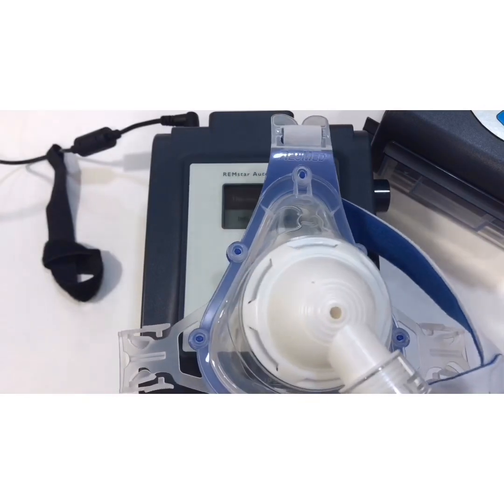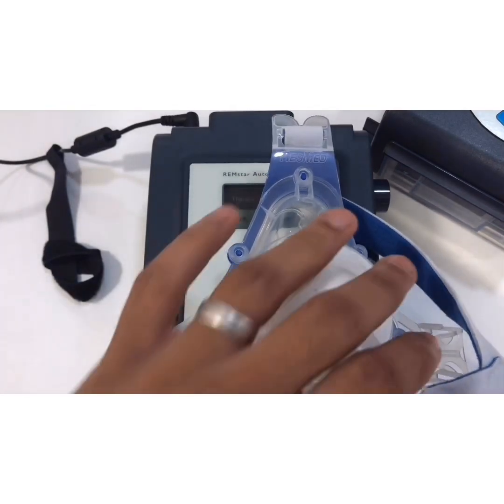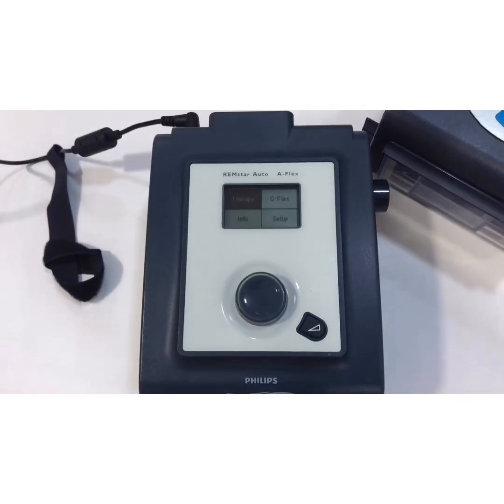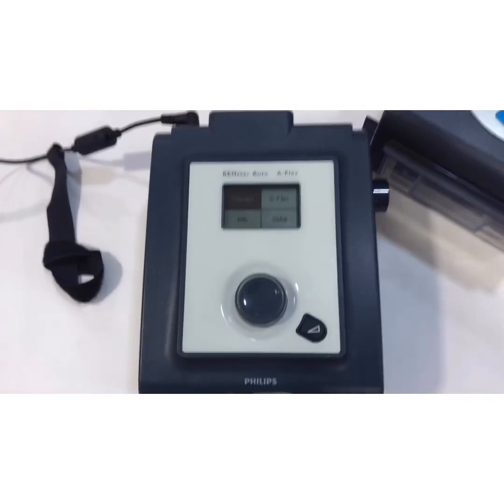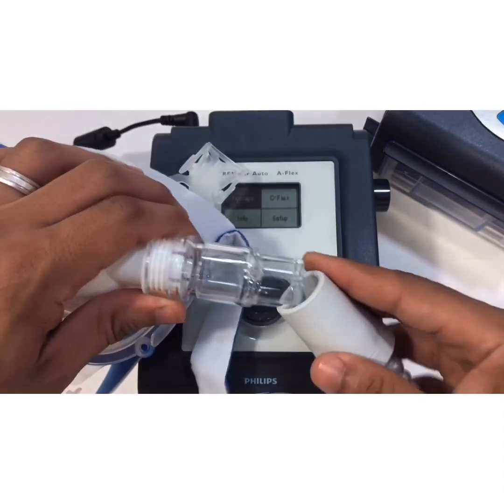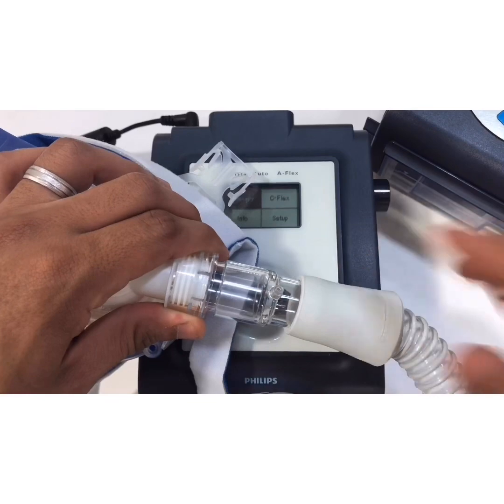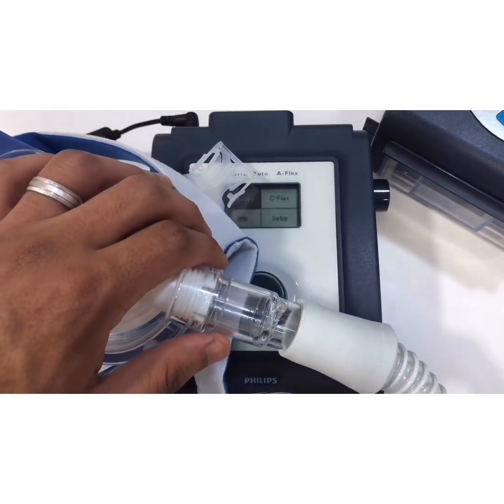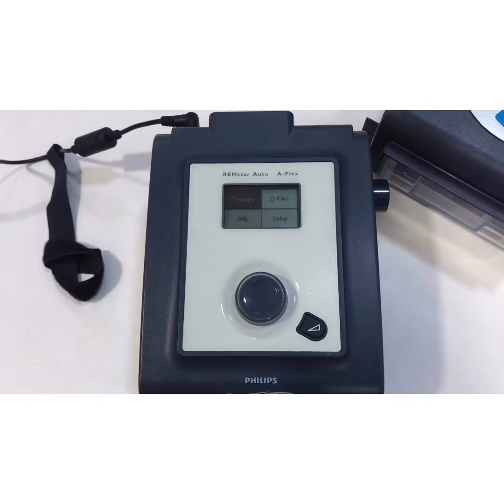In case some patients need oxygen, all we have to do is just add an adapter, and as you see, this is the adapter from the Philips company, so we can put it over here between the mask and the circuit. Then we have a port in which we can add the external oxygen. However, the company suggests if the machine is off, we have to turn off the oxygen at the same time, because the chances of fire are very high if the oxygen is continuously running while the machine is not working. This is what the company says.